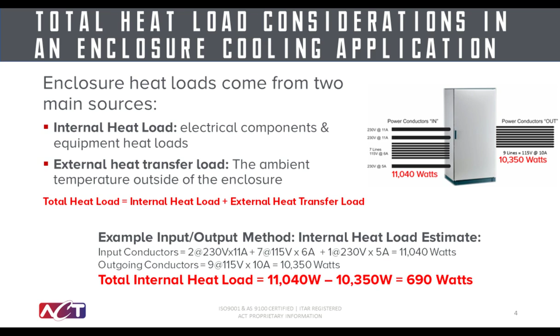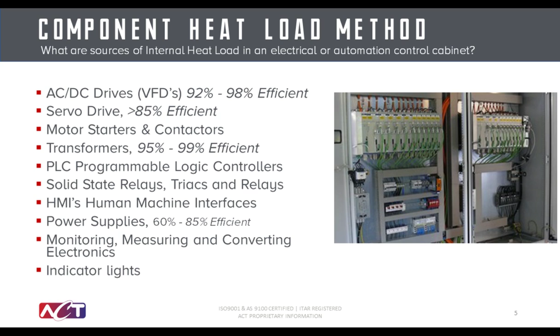The second method we can use to find the internal heat load of the box is the component heat load method. In terms of this method, you will find on this slide general heat loss values of commonly integrated components of electronic cabinets such as power supplies, drives, contactors, transformers, etc. With the general efficiency and manufacturer specifications of these types of components, we can easily calculate the power loss of each module and then add them to find the total internal heat load. On the next slide, we'll discuss how to utilize these to calculate an example of internal heat load.